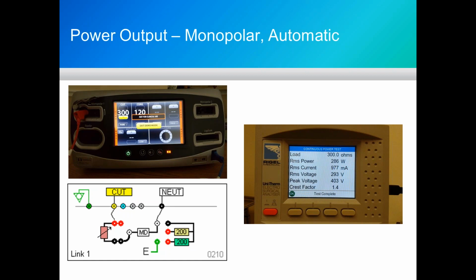Now with the test process for this generator, we're going to do but one test on Monopolar 1, and that is going to be a coag test. And then we're going to switch over to Monopolar 2 and do all our other associated tests on that energy output port. So on the picture of the FT10 itself, you'll see that the upper left-hand side quadrant is energized, telling us that Monopolar 1 is our chosen port.